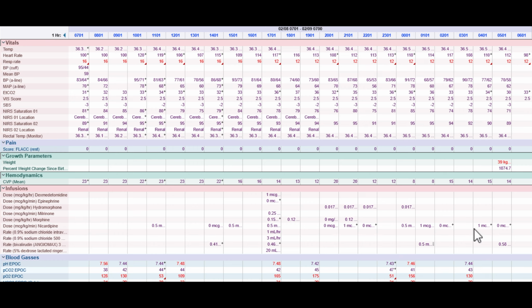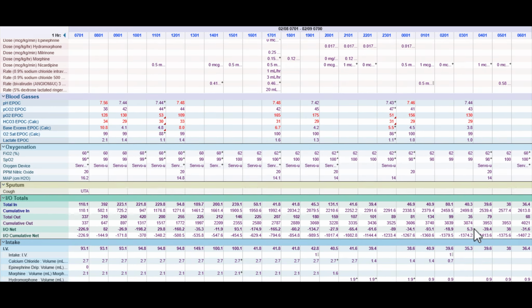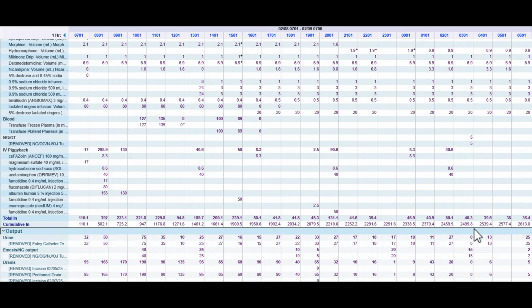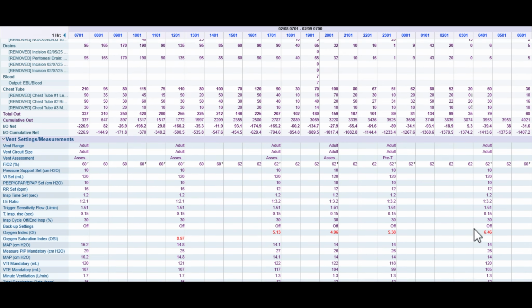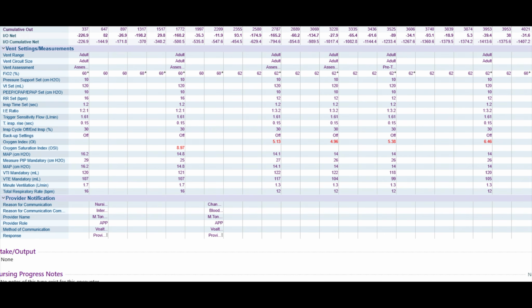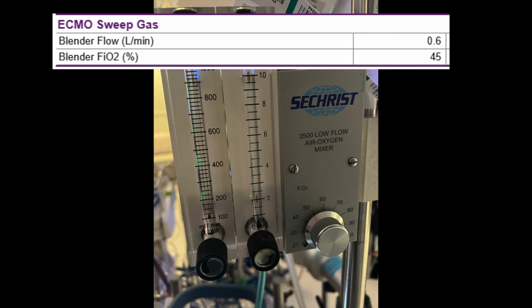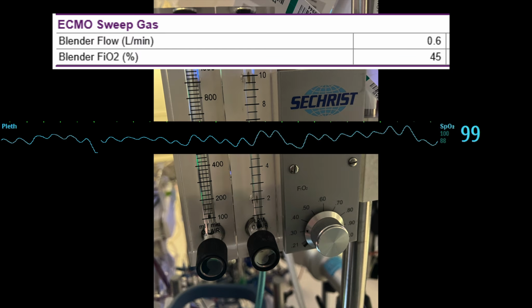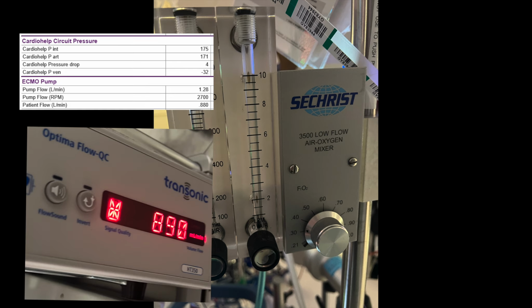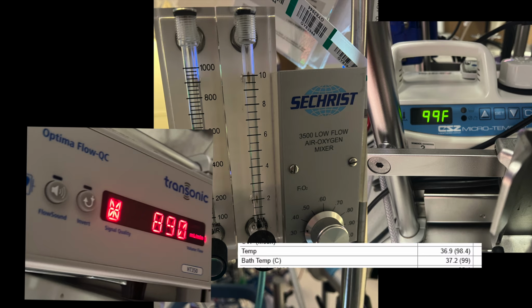Now, a patient on ECMO is going to generate a lot of data, and no one is interested in hearing you repeat all those numbers on rounds. What's most important is change. Has the FiO2 to the oxygenator increased while maintaining similar patient saturations? You might have a problem, such as clots forming in the oxygenator. Flows dropping due to negative pre-pump pressure, probably a problem. Lower water bath temperature, problem.